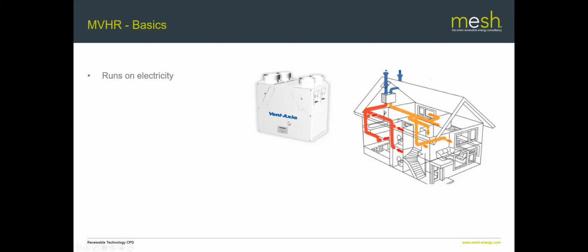Well, obviously you've got the fans in there, so it runs on electricity. Typically you'd be looking at a power demand of less than 100 watts. It recovers the waste heat from the exhaust air, and these systems are pretty quiet. As with anything that moves air, there is a certain amount of noise associated with them, but that noise really shouldn't be noticeable in a well-designed system. So if you have a system that sounds like a jet engine, it's not the fault of MVHR, it's the fault of whoever's either designed it or commissioned it or installed it, and they've got something pretty wrong.